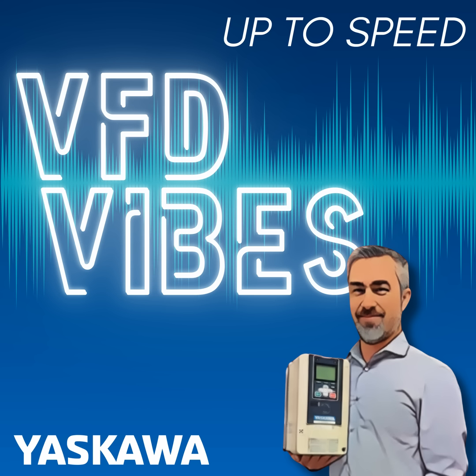These multi-pulse drive packages have been around for 30 plus years. They work well, but they are large, and because of the added components, reactors, the phase-shifting transformer, they're generally less efficient. I know 12 and 18 pulse designs have been around for a long time, and I've also heard that they are mostly being phased out because there is newer, better technology out there. So what are the trends? What is the new technology out there?